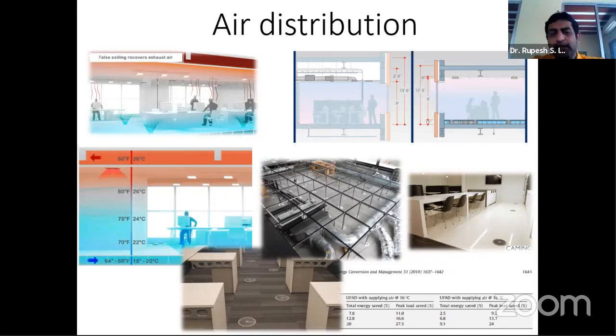Then coming to the air distribution. Of course, we have been using the overhead air distribution now for long, but if we look at physics, physics tells us that hot air rises up. So if hot air rises up, shouldn't we push cold air from the bottom so that it can get heated up from the thermal plume that is created from our bodies, from our equipment, from the sensible sources that are available in the space itself, and then exhaust it from the top. So then underfloor air distribution could also be one of the techniques which could be used in order to achieve a more efficient air distribution process.